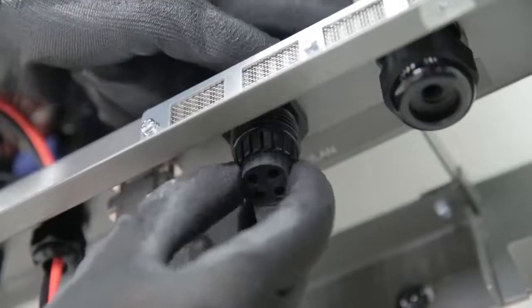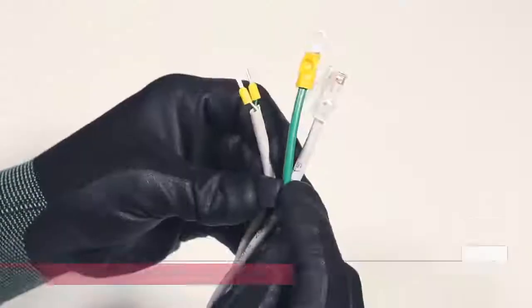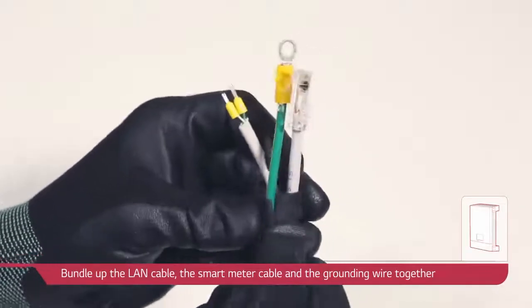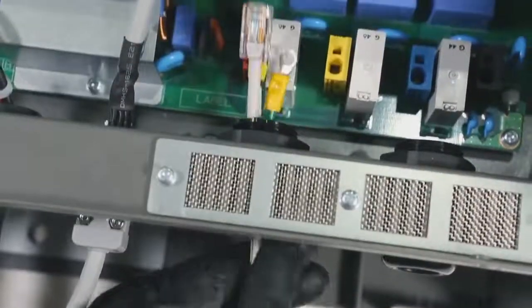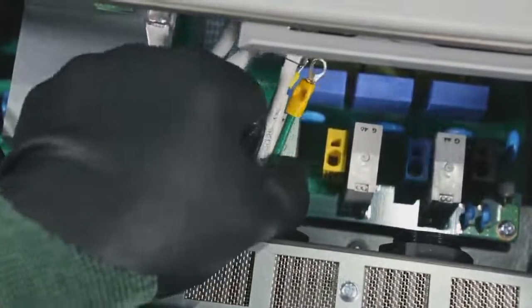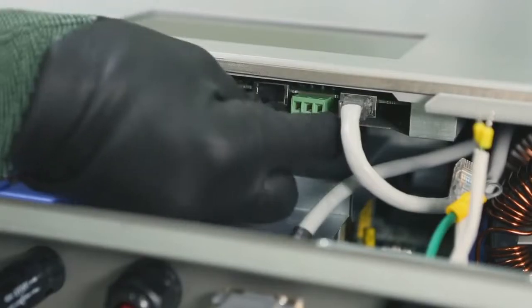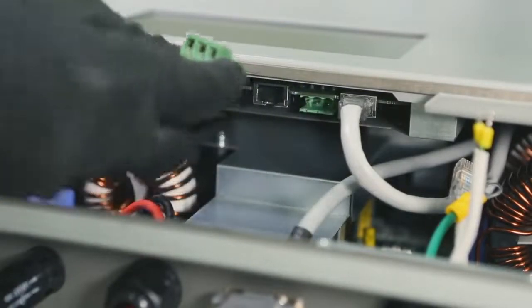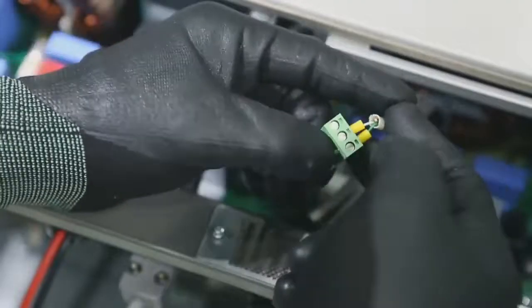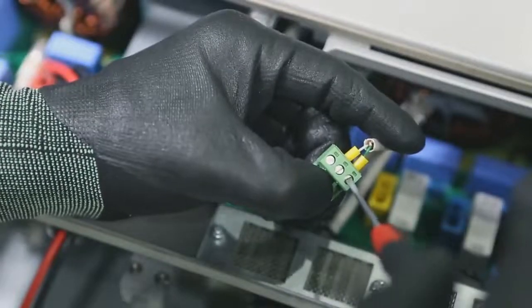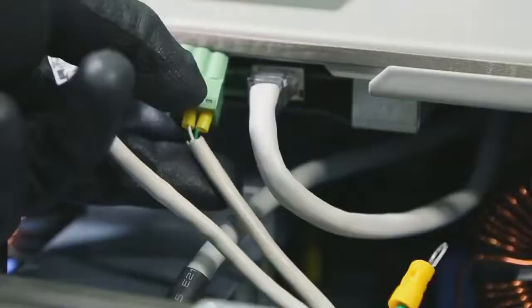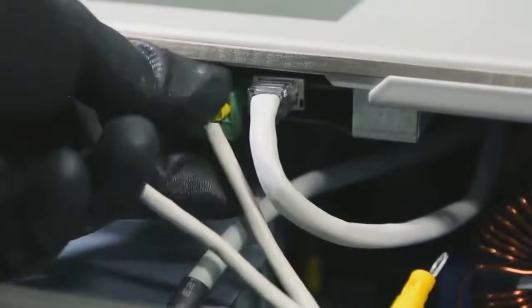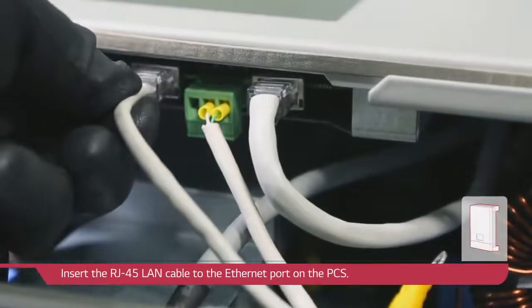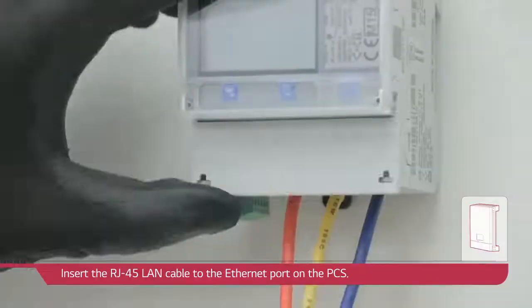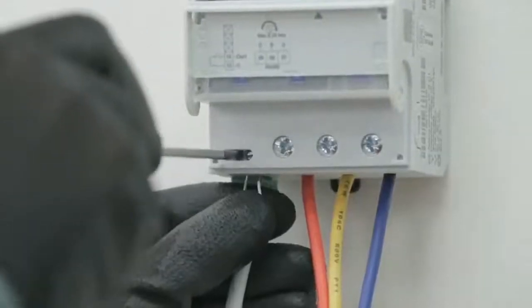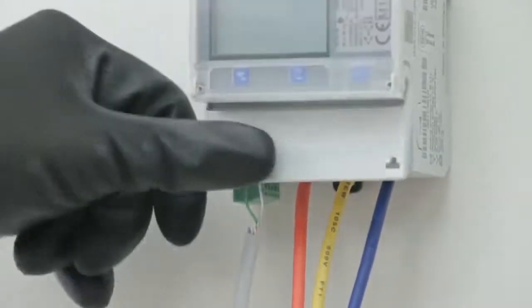Release the cap and the rubber from the cable gland and bundle up both the LAN and smart meter cables using the rubber. Push the cables into the opening of the rubber fitting. Detach the green smart meter plug from the backboard of the PCS's front cover. After connecting the 2 wires into the smart meter plug, insert the plug into the smart meter terminal, and insert the RJ45 LAN cable to the Ethernet port on the PCS. Insert the other end of the stripped wires to the smart meter mounted on the wall.